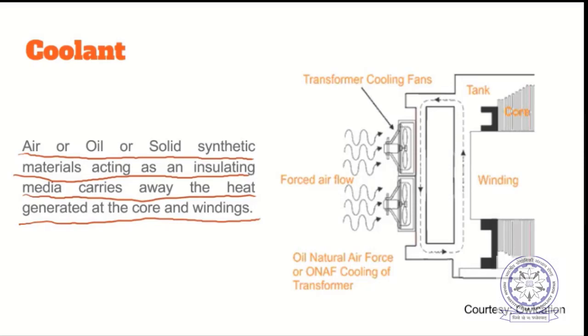So heat is generated at the core and windings, and the medium which acts as insulation as well as a heat transfer medium is known as coolant. Air also can be used as coolant, as can oil or solid synthetic materials such as epoxy. Of course, when you use solid synthetic material, it is basically used as insulation, but it will transfer the heat as well.